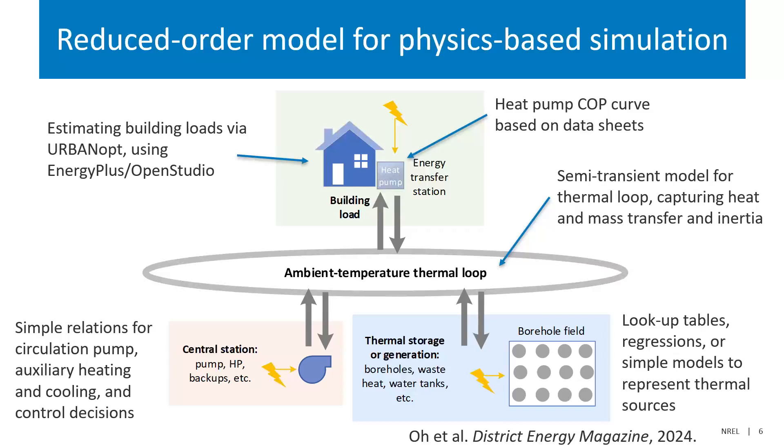Plugging in and exchanging heat with that loop, we have all of the buildings, which requires doing some building modeling and understanding how heat pumps perform given different entering temperatures from the main thermal loop. There are also thermal sources and sinks — we're mostly focused on borehole fields, relying on collaborators including Lawrence Berkeley National Labs for detailed borehole performance modeling. We also model circulation pumps, an auxiliary heating and cooling system, and a control decision architecture that determines how all these pieces run together.